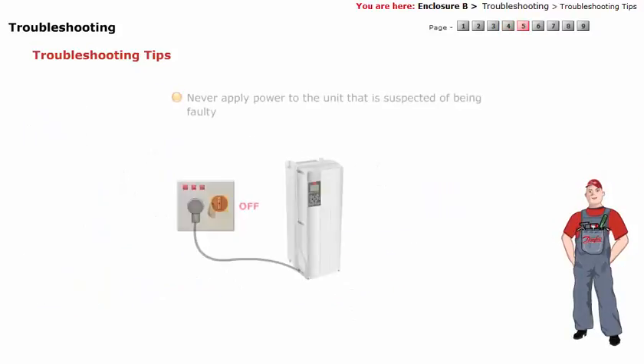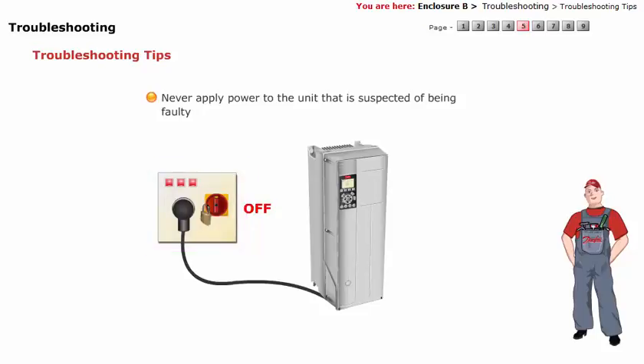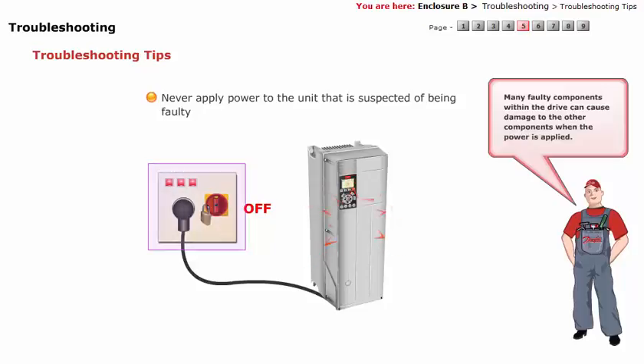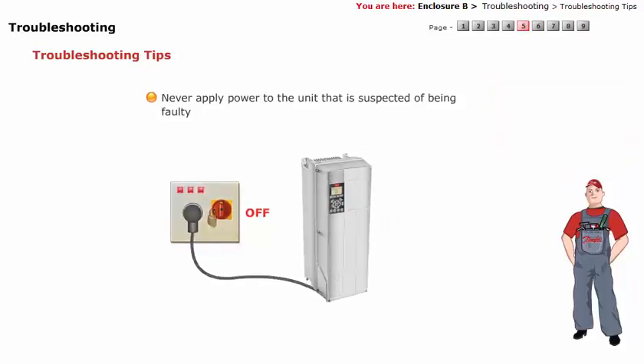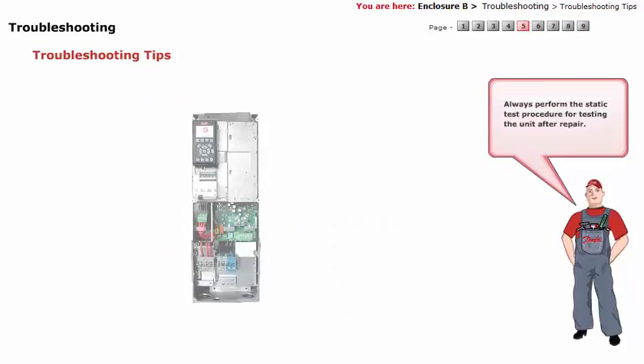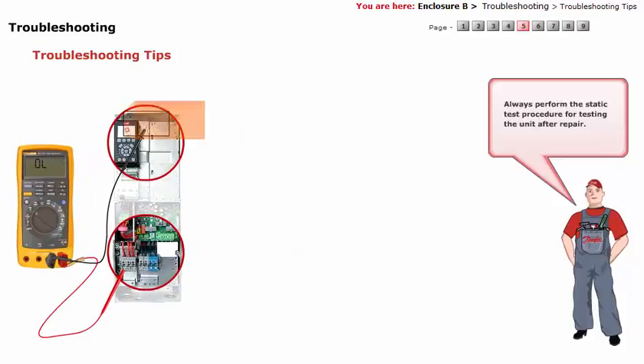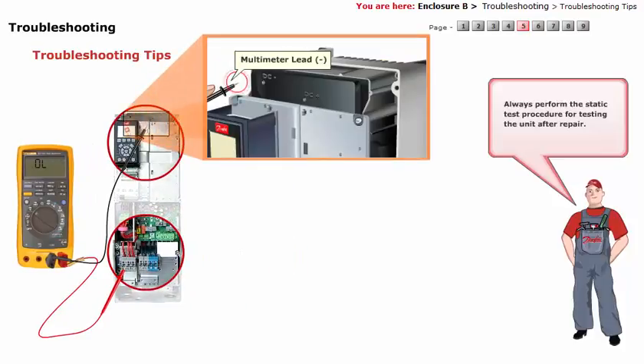2. Never apply power to a unit that is suspected of being faulty. Many faulty components within the drive can cause damage to other components when power is applied. Always perform the static test procedure for testing the unit after repair.